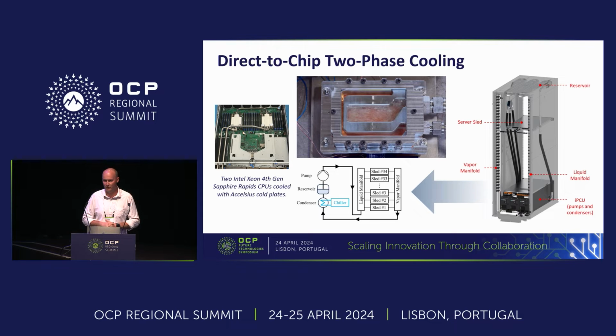We have a manifold with quick disconnects for providing liquid to the servers, and also a vapor manifold to collect the vapor that comes off the chip and bring it back to the CDU. The main difference you'd notice from the outside is a reservoir located at the top of the rack. The reservoir allows for expansion of liquid and vapor during phase change, which helps prevent cavitation and other issues during startup and rapid changes in power load.